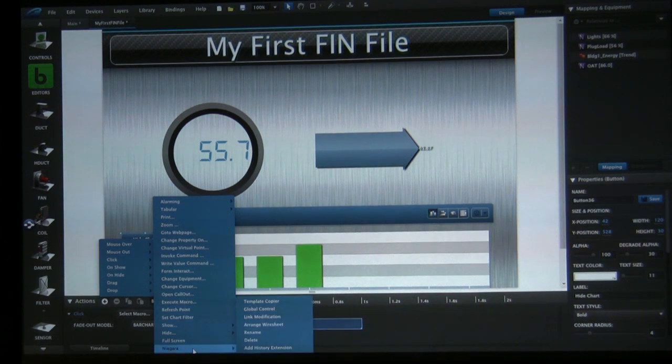Anybody that wants to create their own app or create their own wizard or create their own appliance, you could literally do server-side stuff from FinBuilder. So you could take a bog file, and imagine you wrote a little wizard for deploying thermostats. And I could have a pre-made set of logic hanging out, and when somebody says add a thermostat, I could grab that bog file, make a duplicate of it over in Niagara, change all the links to it, bring along the graphics, and effectively build an appliance using FinBuilder.